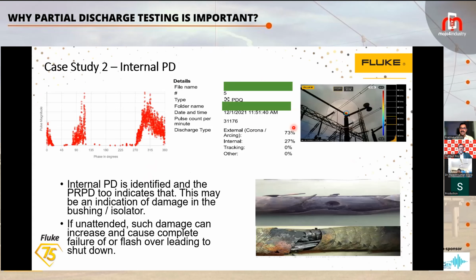And in the next example, here you can see the PRPD curve is different. And here also you can see 73% of the acoustic partial discharge is coming from the corona, and 27% is coming from internal. Okay, this means the bushing or the isolator has some internal damage. It has an internal arcing happening, and this may create a problem very soon.